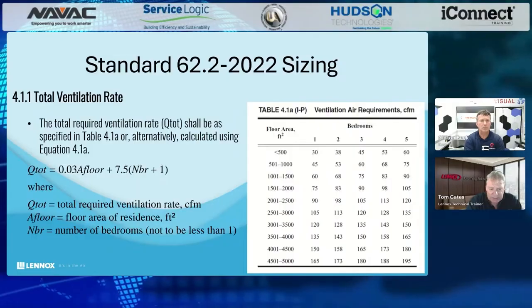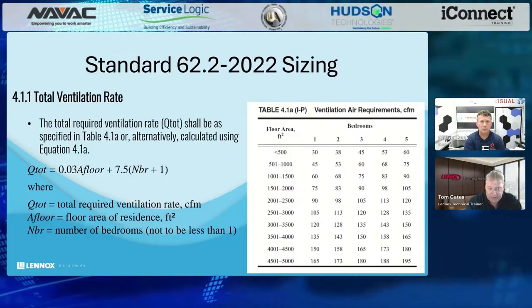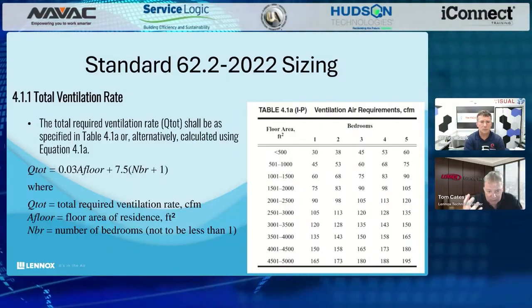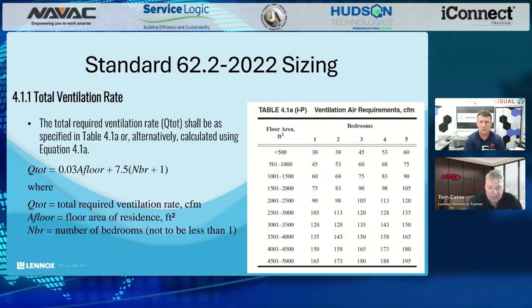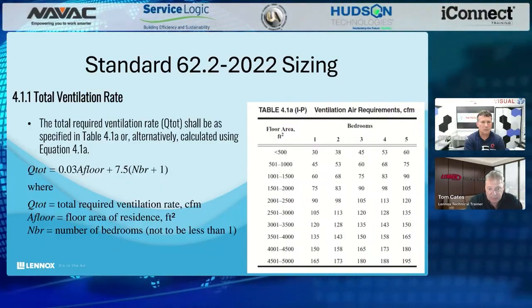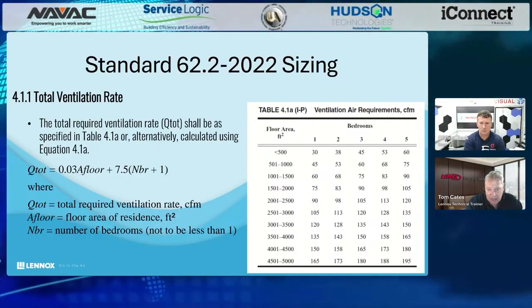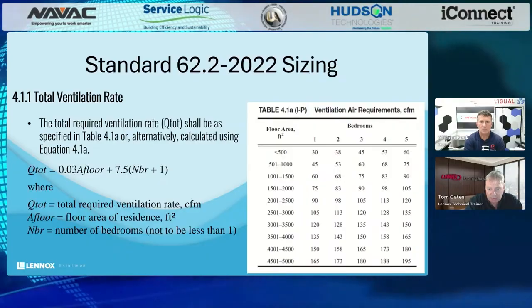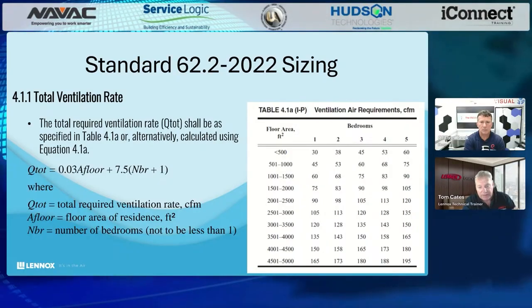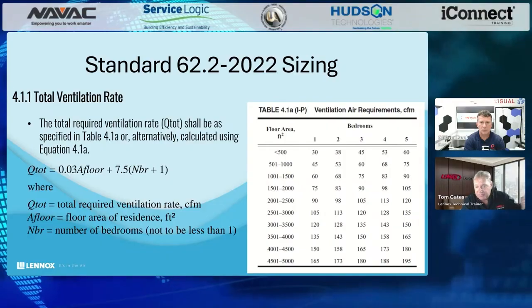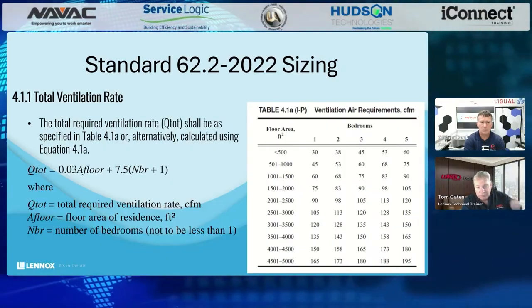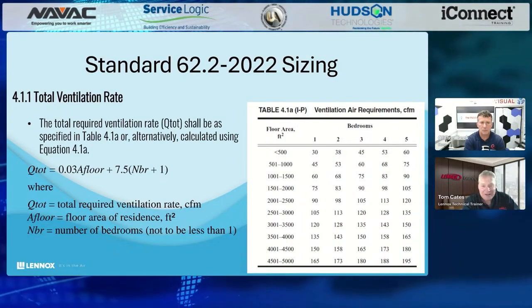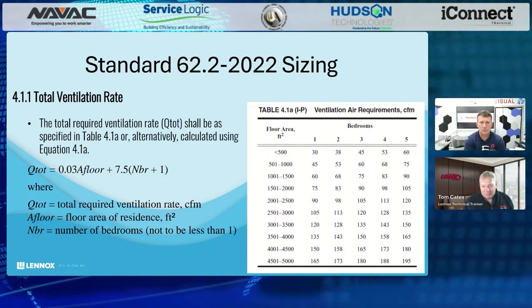So, if I look at this here, if we had a 2,000 square foot house, so in the 1501 to 2000 range, and it's 3 bedrooms, we need 90 CFM of fresh air being delivered to that space. I can do that with a single 90 CFM bathroom fan. I could do it with two 45 CFM bathroom fans, or a combination of a bathroom fan and a range hood.